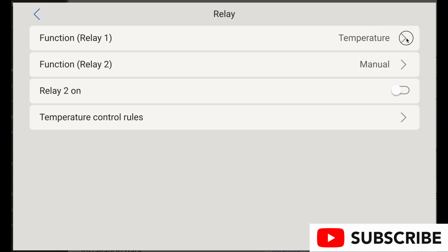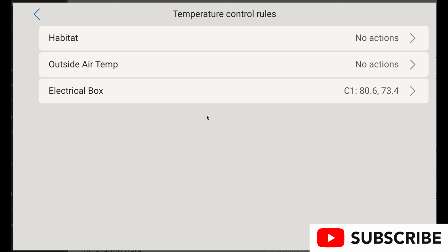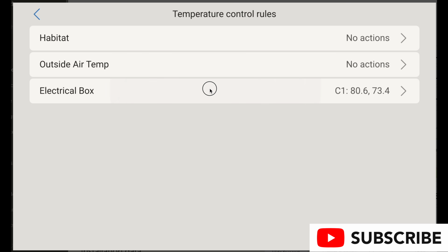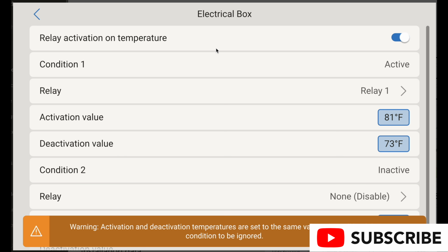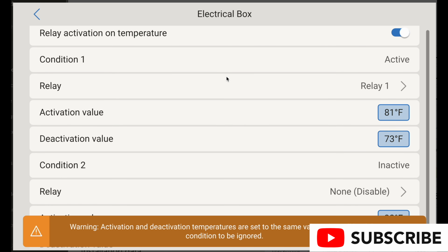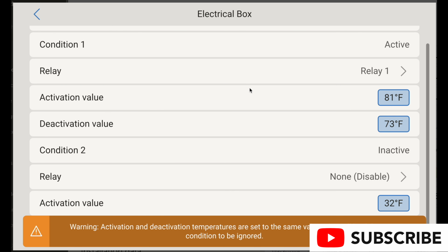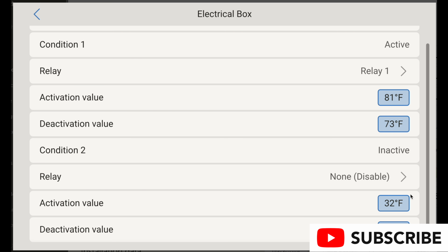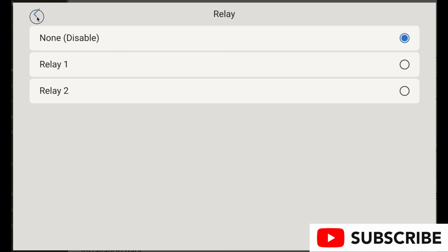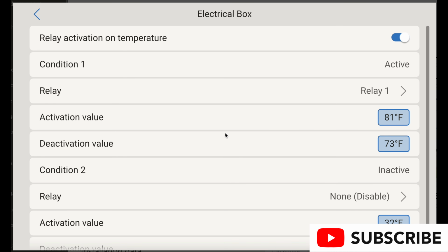Now we're back into our relay, just checking our settings. So we have the temperature there. We can see our control rules for the electrical box, and the relay is going to activate on temperature. The condition is active: relay 1 activation value is 81F, deactivation value is 73F. Then there's a condition 2, and we have it on none. If you have activation and deactivation values the same, it's just not going to work, but we don't need a condition 2, so we're just going to let those sleeping dogs lie.